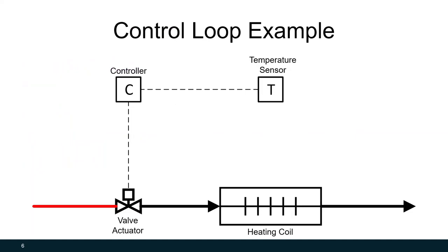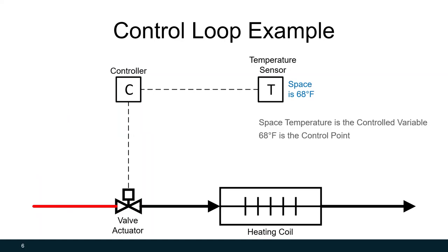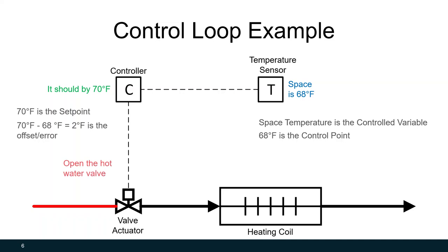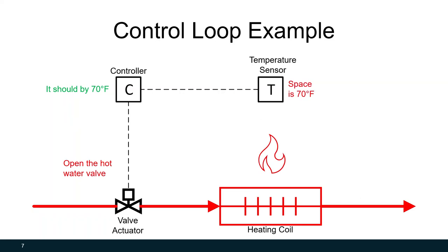Here we have a hot water coil that's heating a room. The temperature sensor detects that the space is at 68 degrees. Because the heating coil is heating the room, our controlled variable is space temperature, and 68 degrees is the current control point. That sensor sends an input signal to the controller, which compares it to its set point — currently set at 70 degrees. The difference is a 2-degree error. The controller is programmed to react to this 2-degree error and sends an output to the hot water valve to open, allowing hot water to flow to the heating coil and heat the space, until the space gets to 70 degrees.